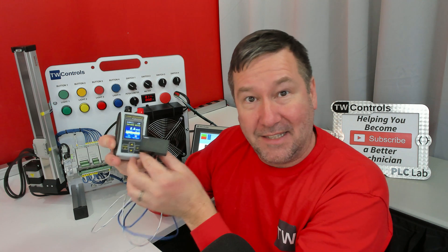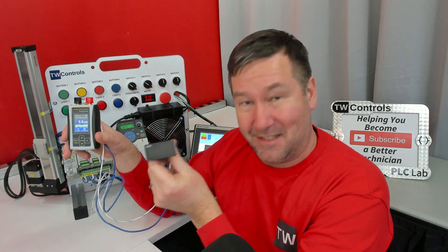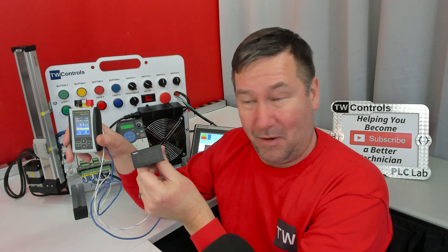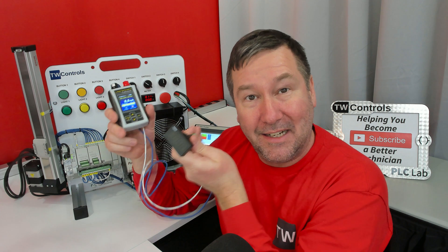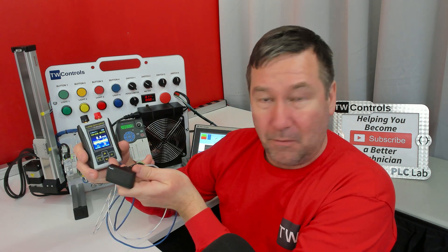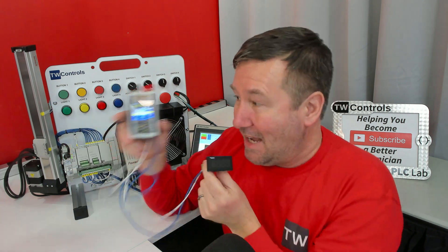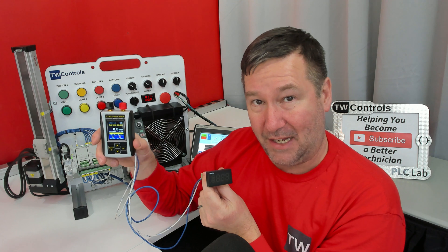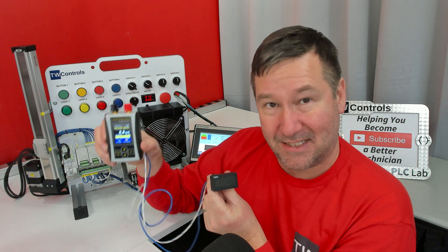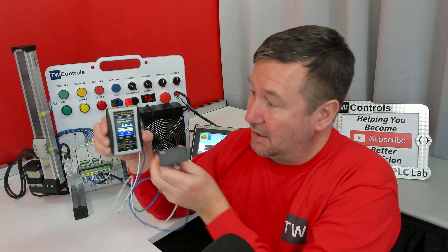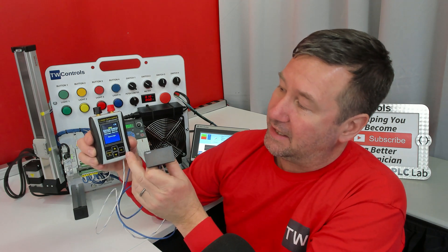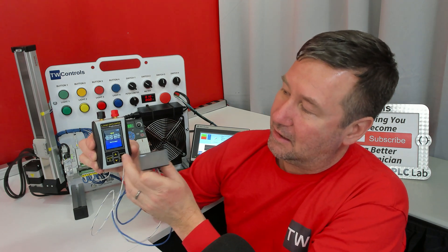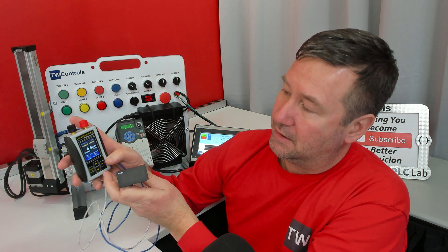Now, since I did not put a power supply in the circuit, such as a two-wire device would need, then it can have no current and we're getting the open wire. I need this to be the power supply. So that means this needs to run in current source mode in order to do this. So I'm going to hit cancel, we got a current source mode.